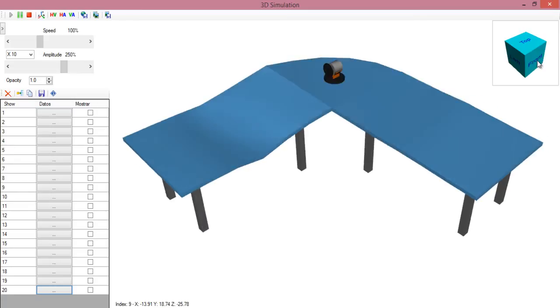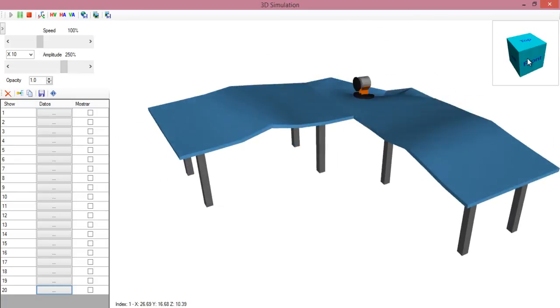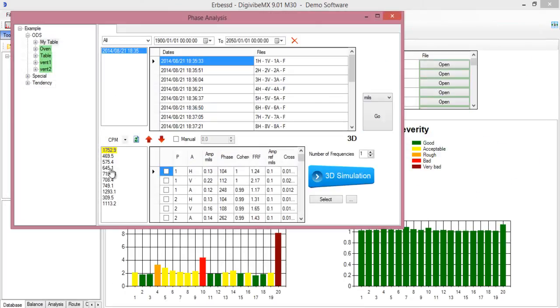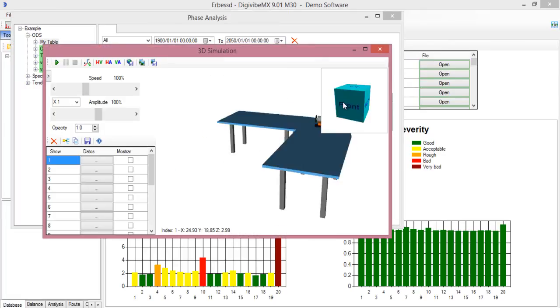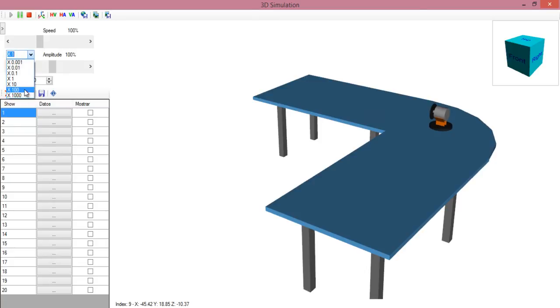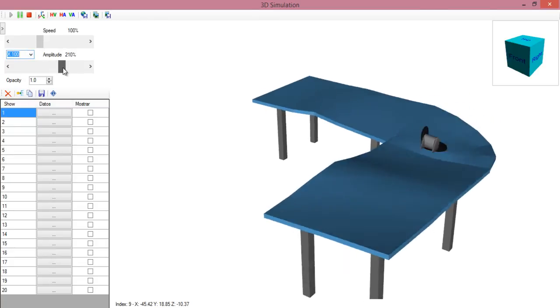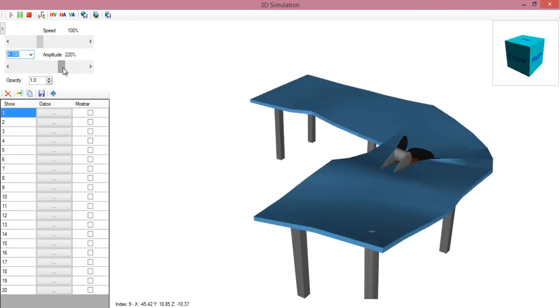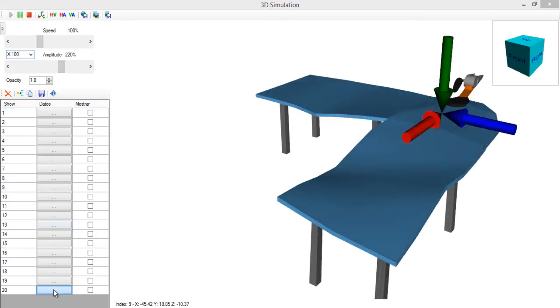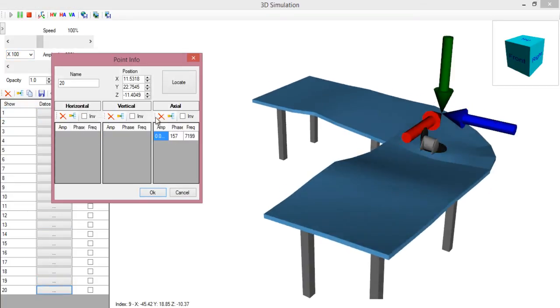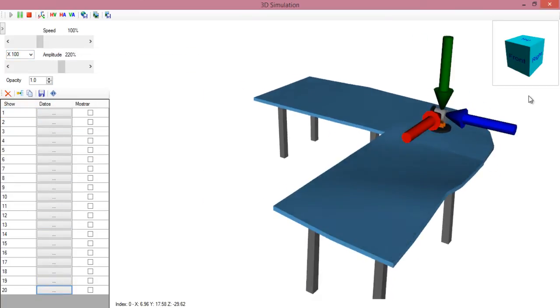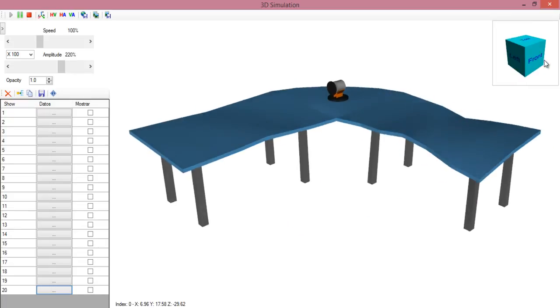Now this motor has a second vibration frequency at 7200 CPM, which is electrical noise. Let's select this frequency and see how the table moves at this particular frequency. Now the displacement is lower, so we need to increase the amplitude. We will remove again the vibration in the motor. Now take a look to the table and how it moves in high frequency. This is very interesting.